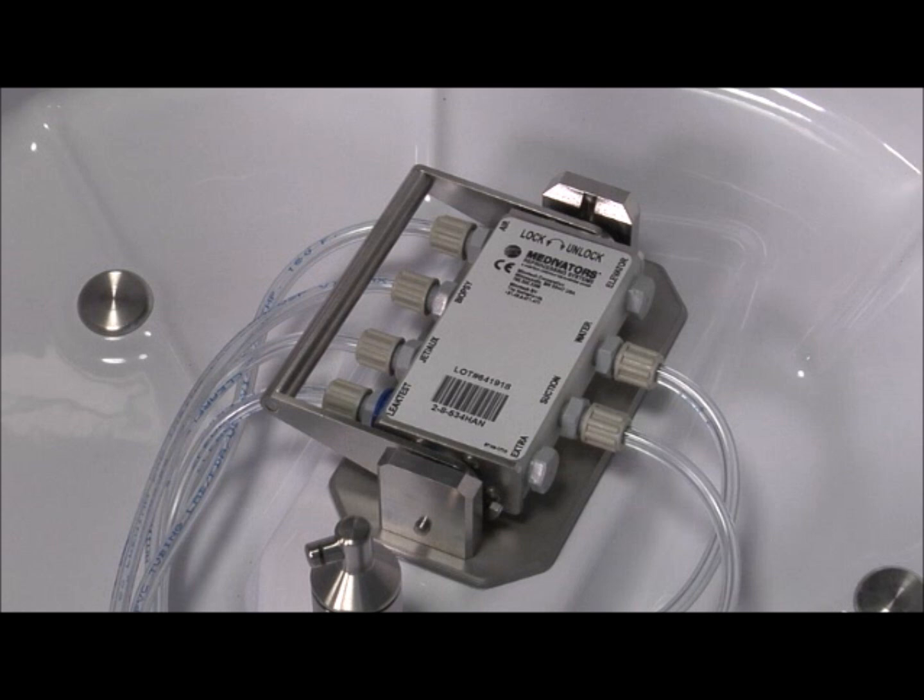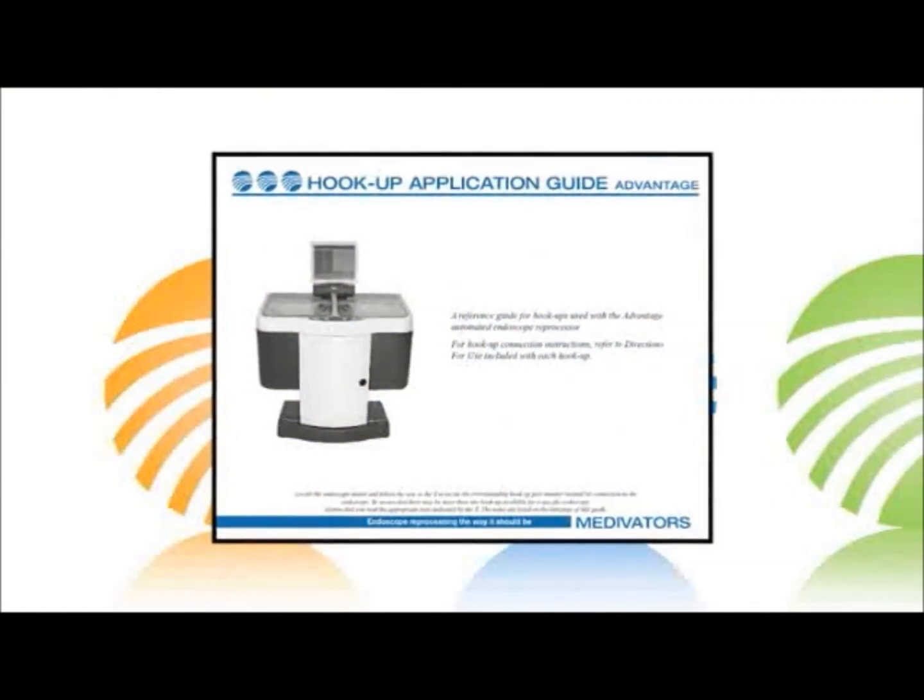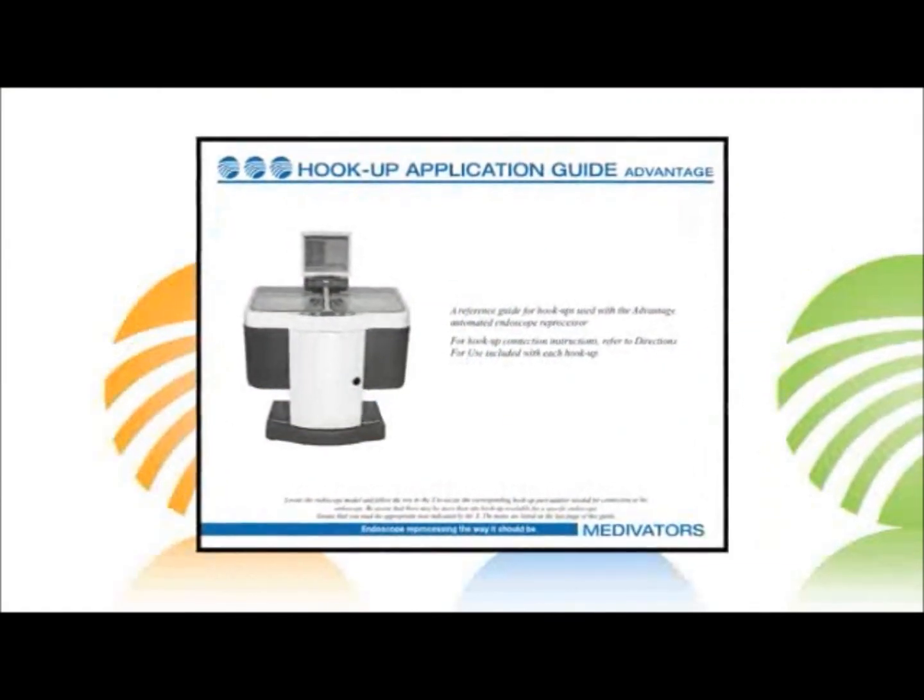Endoscope hookup block connectors must be purchased along with your Advantage Plus. Matching the scope to the correct hookup block is critical to proper reprocessing of the endoscope. Use the connector guide to ensure you are using the proper connector.